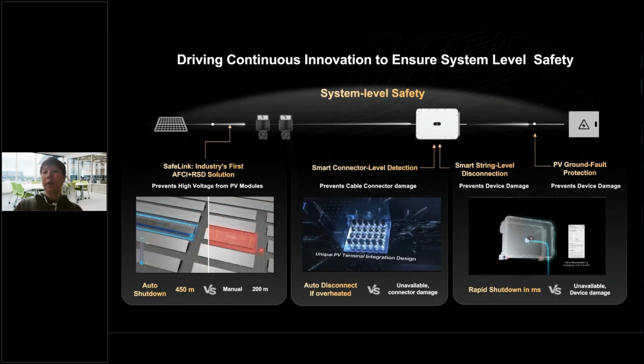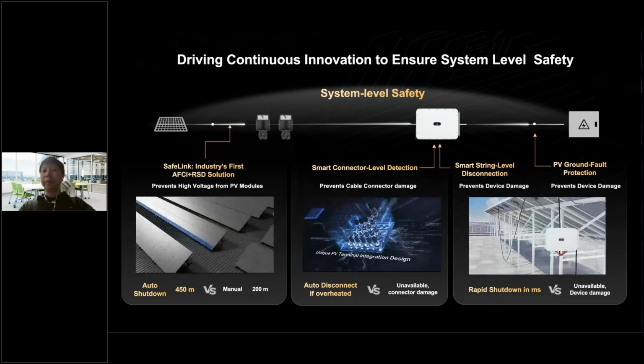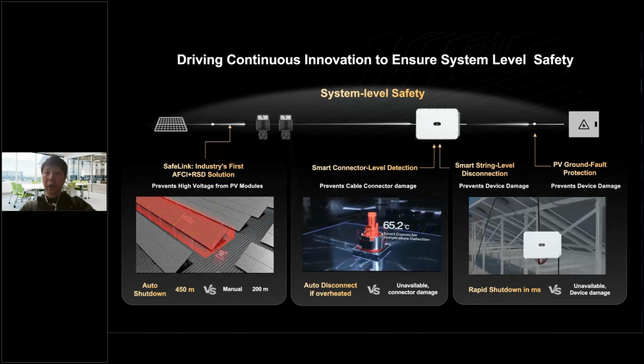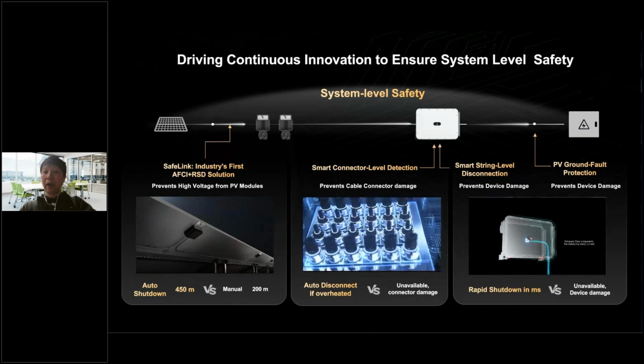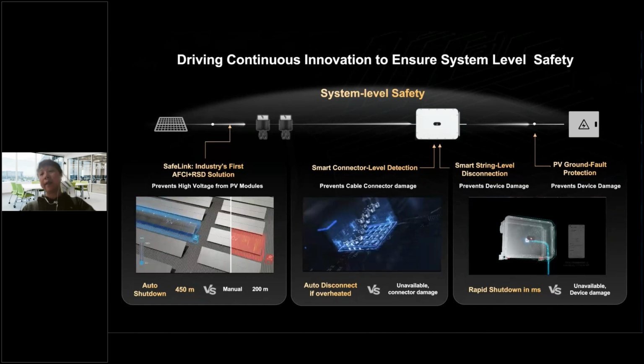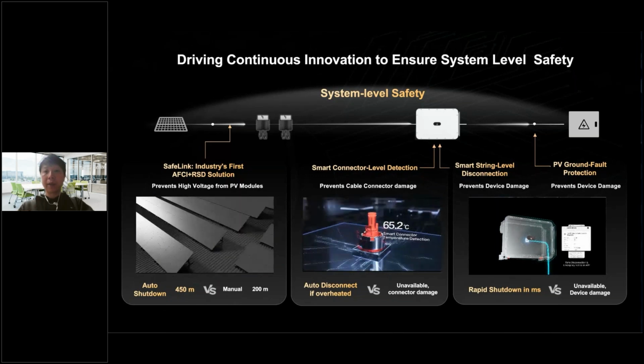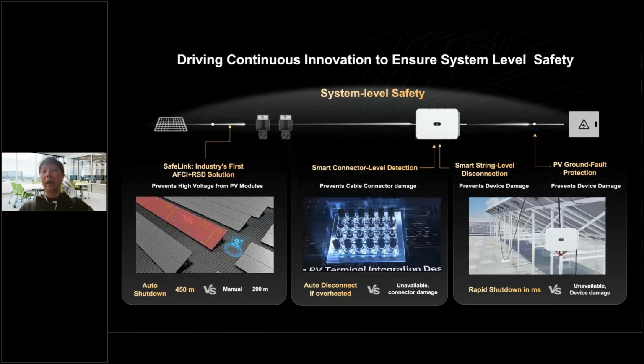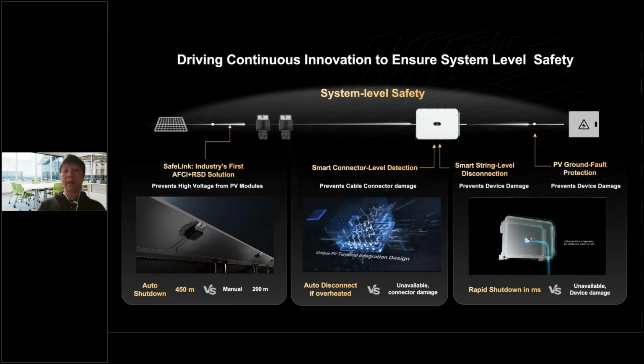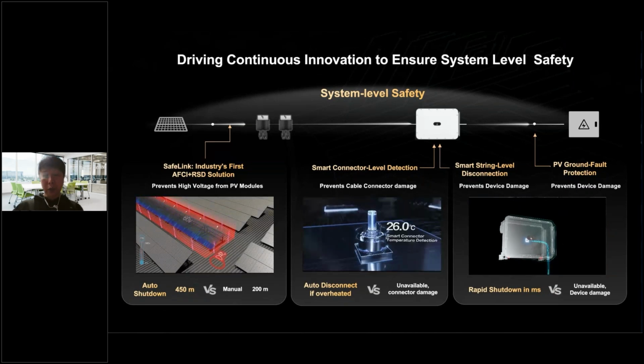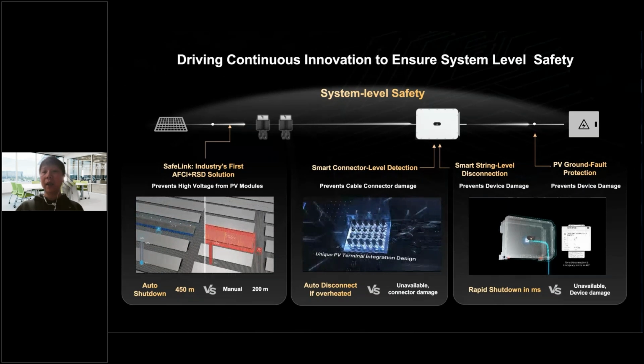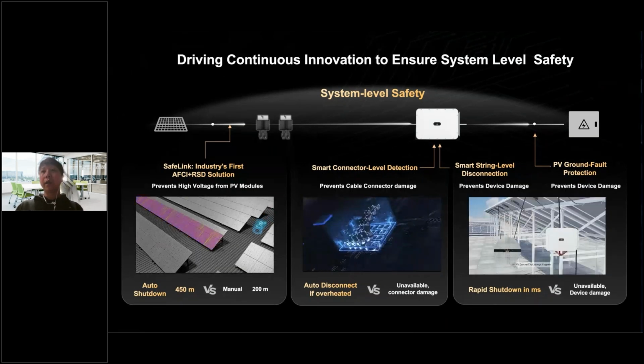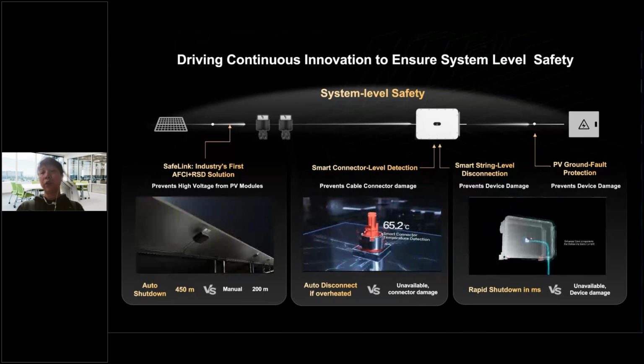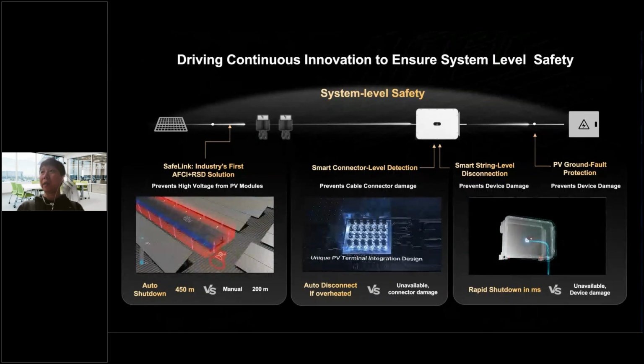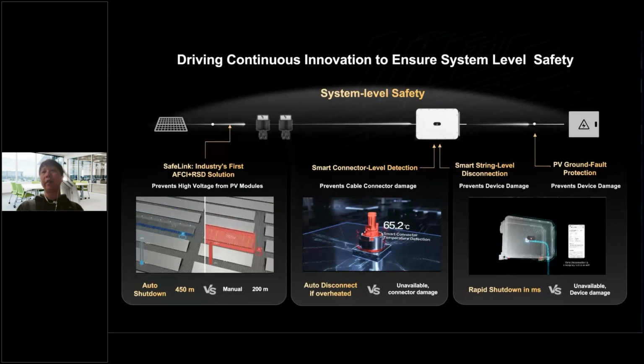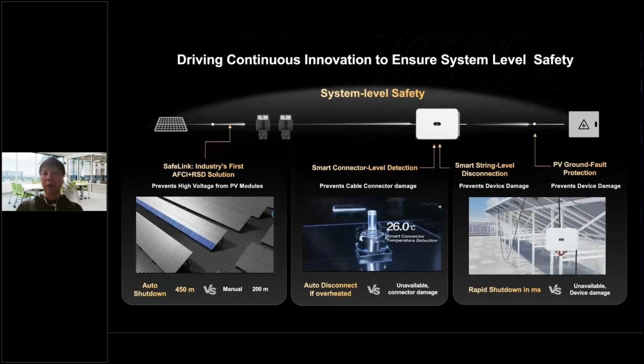And the last one is about the PV ground fault protection. This one, we also introduced for the first time in the 150K, because we have observed that on the DC side there are sometimes short circuit problems, and the result of the short circuit is a very high current, which will cause fire or explosion of the inverters. Talking with some of our partners, they mentioned cases they have observed in the field with other vendors who don't have this kind of PV short circuit protection. The inverters actually exploded, and the cover of the inverter flew about 3 meters away, because they don't have this kind of safety feature.